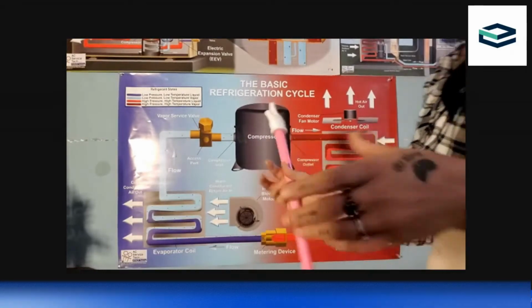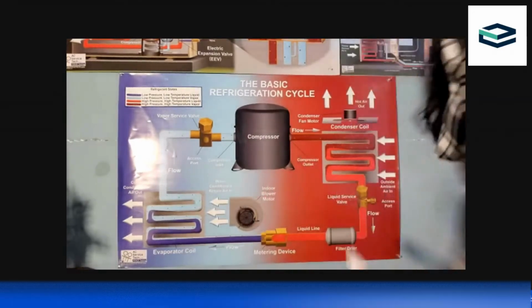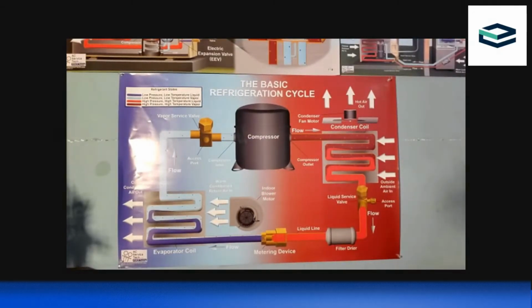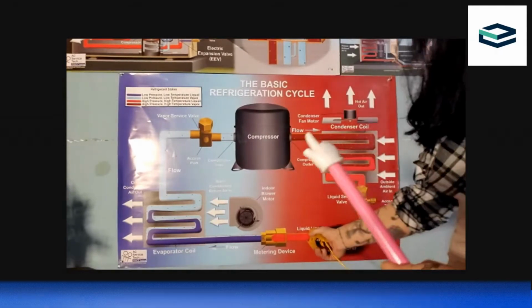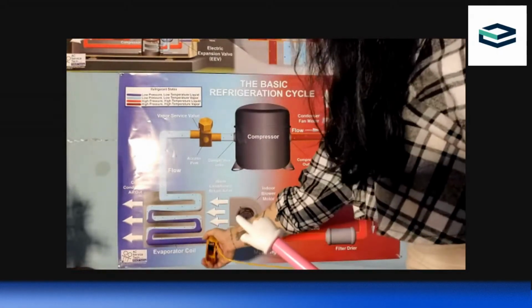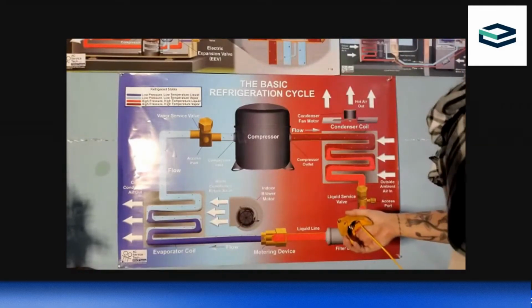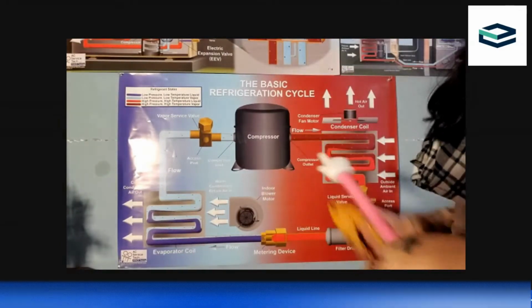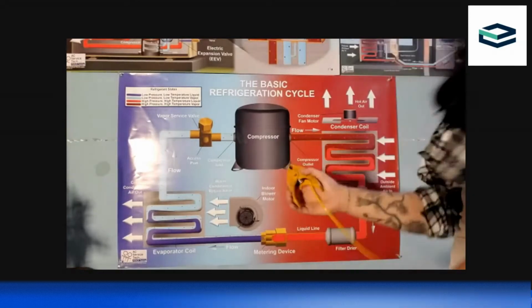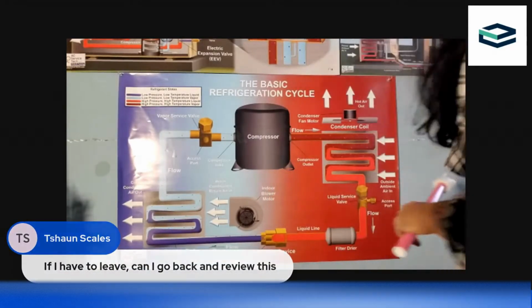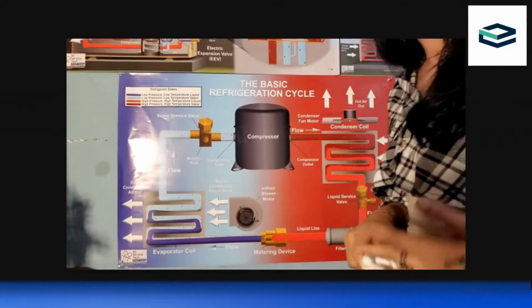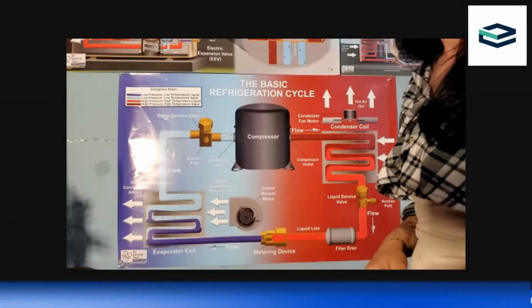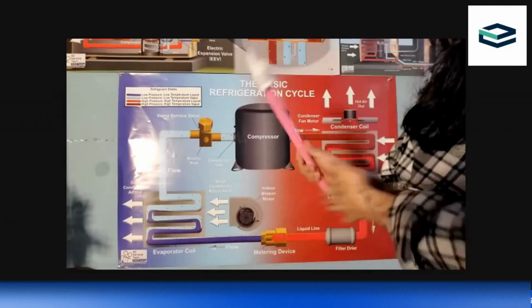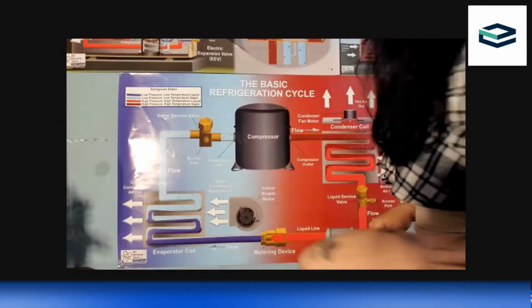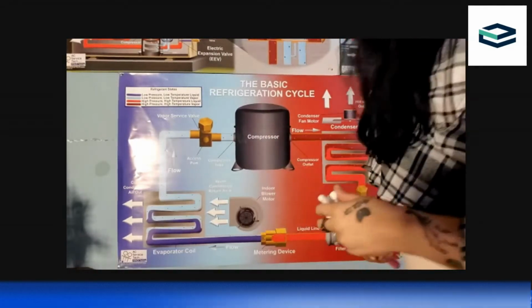So again, you could do a non-invasive system check and get those temperatures. We're using those clamps that I showed you. I'll actually grab one real quick. We're using those clamps. We're putting them on the liquid side, on the vapor side, and then we're taking that temperature and the temperature difference between them. You can do that without gauging up to the system. You just put the temperature clamps on. You can also take that temperature with a thermistor attached to your meter, or with a temperature probe you could tape to it. There are lots and lots of ways to check this without gauging up to the system. But one way is to gauge up. Your gauges will always tell you that.